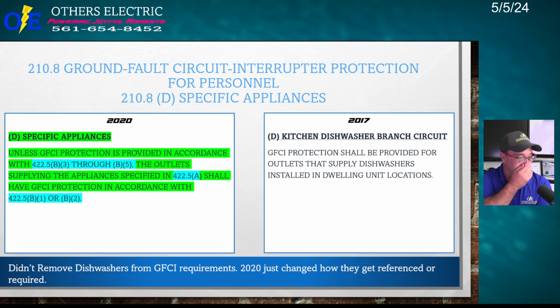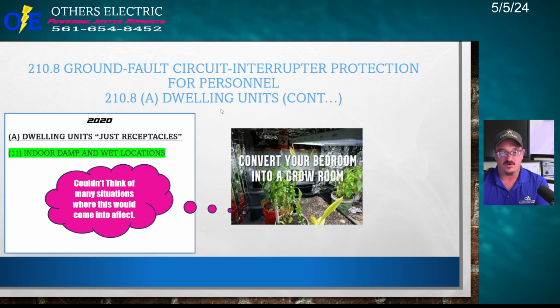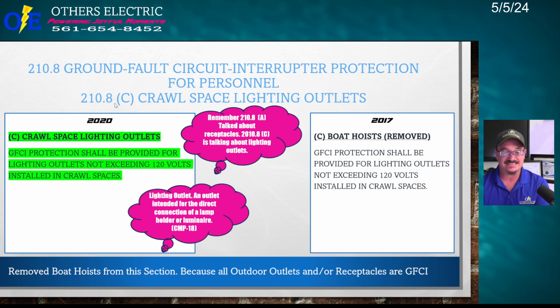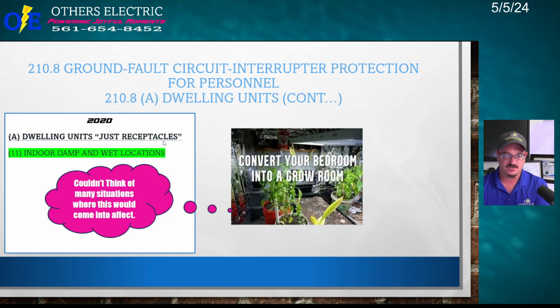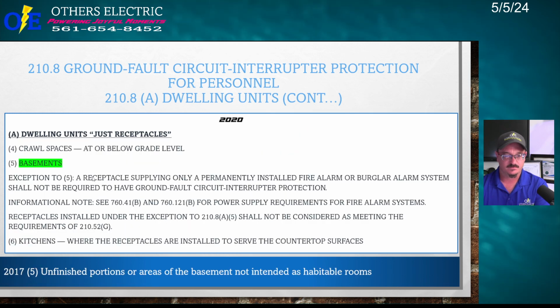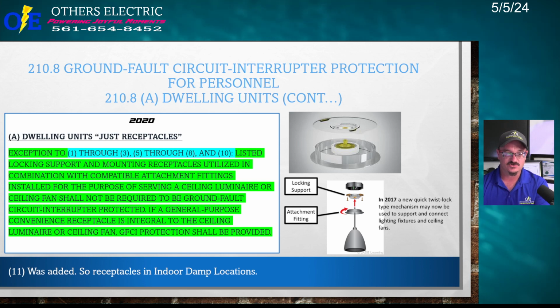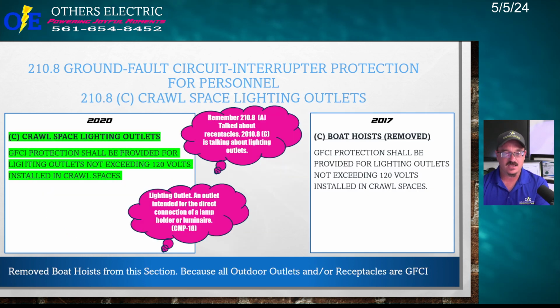sorry about that. I'm going to have to edit that out. Okay, so remember, we are talking about A, that's for dwelling units, receptacles, right? Now we talked about 210.8C, which is talking about crawl spaces specifically, right? And they're talking about lighting outlets. So lighting outlets, now I bet you're wondering right here, why are they talking about crawl spaces? Because if you look in 210.8A, it already says crawl spaces. But you got to remember, 210.8A is talking about what? Receptacles. So now 210.8C is talking about lighting outlets.